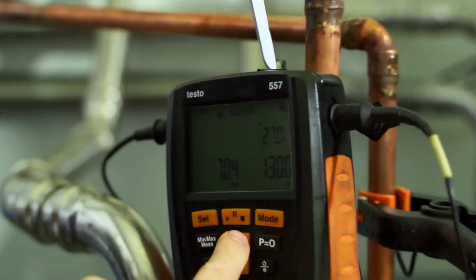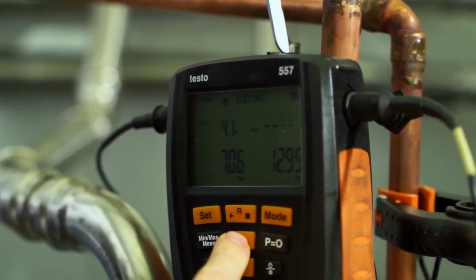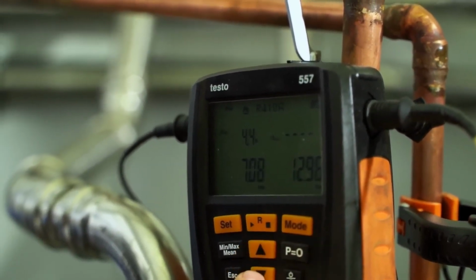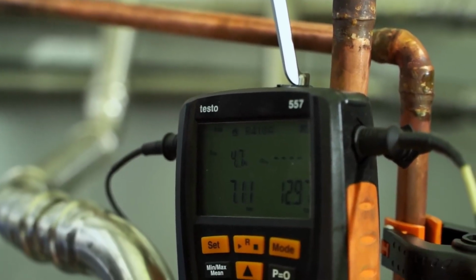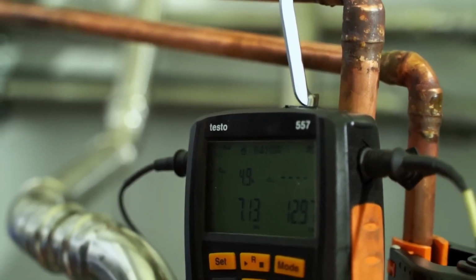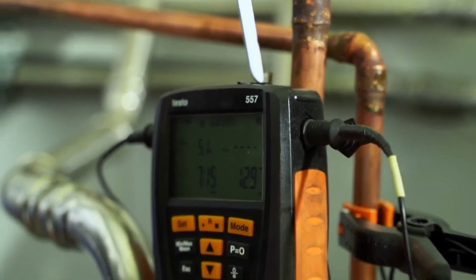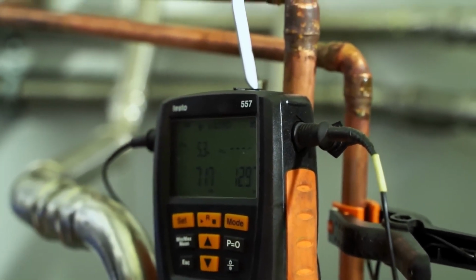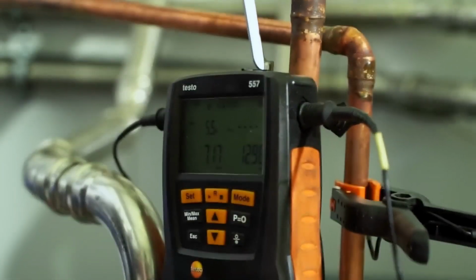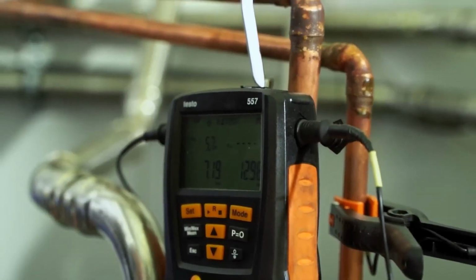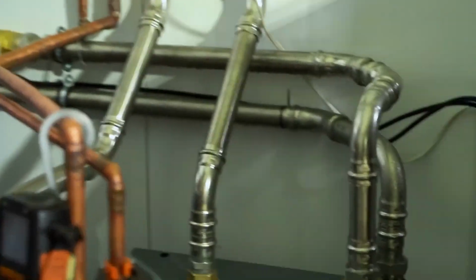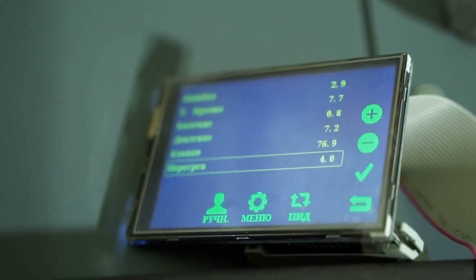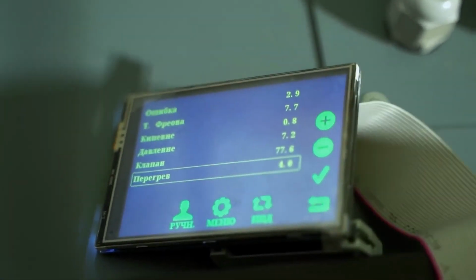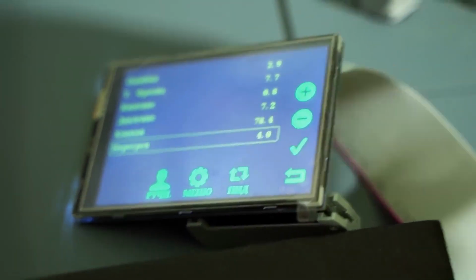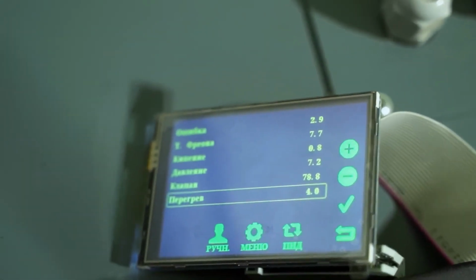Alright, we are observing the superheat. We have 4 degrees and there is currently no subcooling present yet. We need to add more refrigerant so that the condenser gets a bit flooded and we get subcooling. Right now it's at 6. Now the TXV will react to the increase in subcooling and let more refrigerant through. Here you can take a look right here. This is how the TXV works. The electronic one is trying to regulate. It's trying to maintain a superheat of 4, but it needs to stabilize. It will gradually get there.